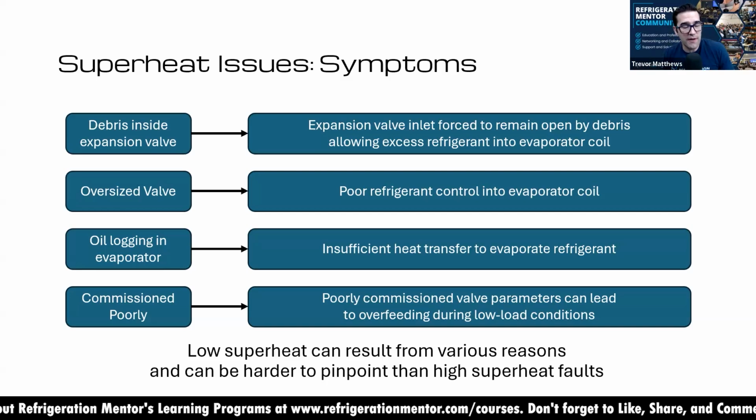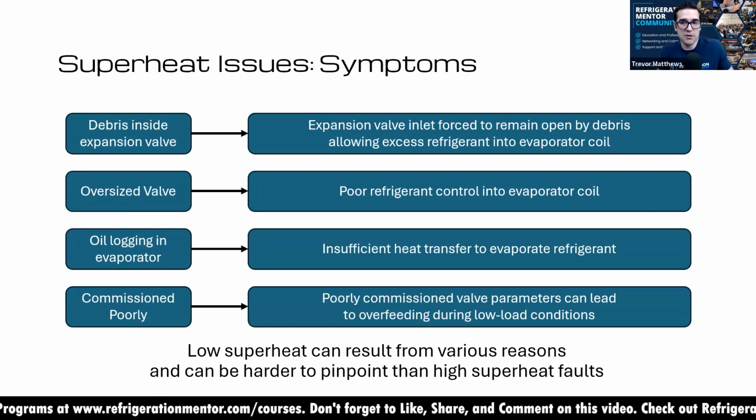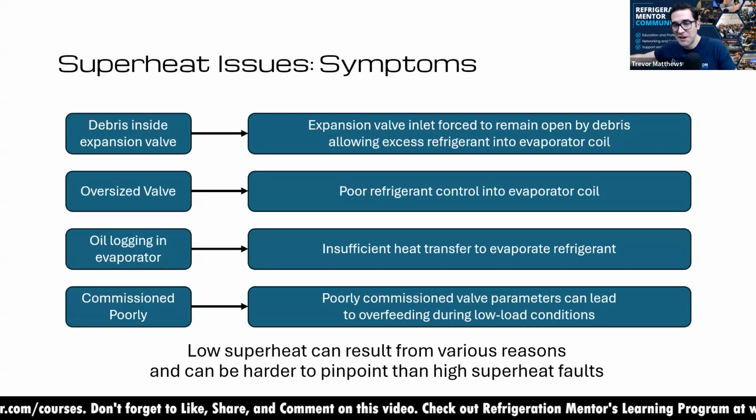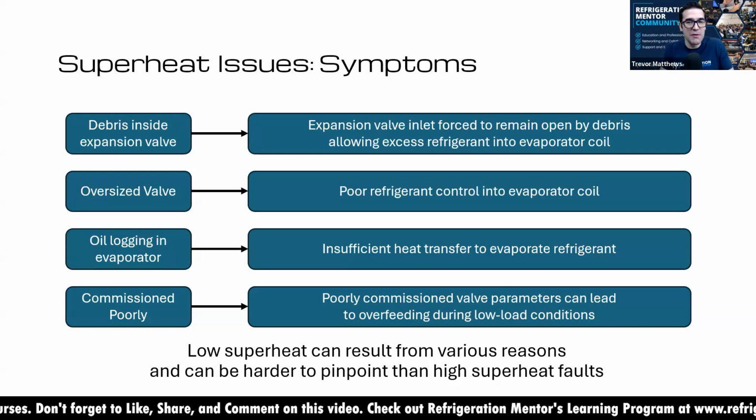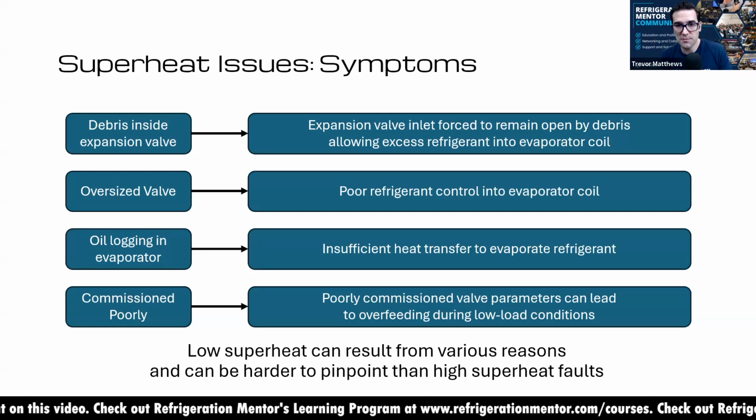I find it so much easier to troubleshoot a case when you have all these checkpoints. Before, when I was in the field and on the tools, I had a set of gauges and I put it on one case and my temperature probe, and I had Cooper and say Yellow Jacket, and nothing was logging. So I just saw it at that moment in time. And I walk away, go to check another case, and then I come back and it's different. I'm like, okay, well, what's happening? Now with the trend graphs and these controllers, and really any manufacturer now with case controllers, they're doing a great job with the logging features as long as it's set up and you have the temperature probes. It helps me so much.